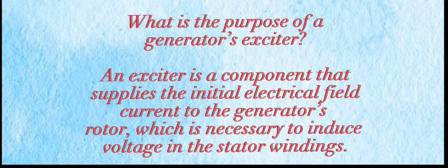What is the purpose of a generator's exciter? An exciter is a component that supplies the initial electrical field current to the generator's rotor, which is necessary to induce voltage in the stator windings.